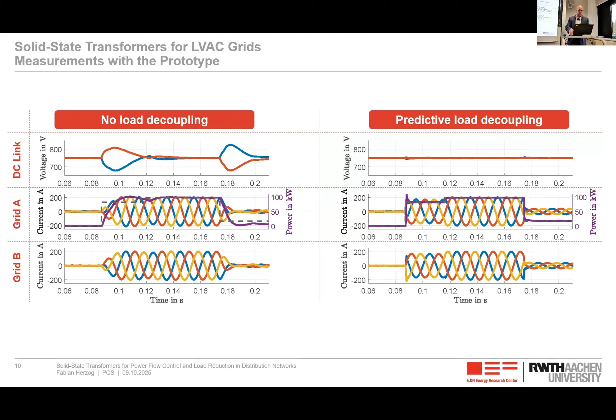The control of the DC-DC converter is very dynamic, while the AC-DC converter is mostly limited by the control bandwidth and by the inductive components on the grid side. But if we basically tell our AC-DC converter, hey, a load step is coming now, and this is the load step, it can use a model to predict which current it has to set. Then we see a very flat DC voltage and a very dynamic current change, basically in one step of control.